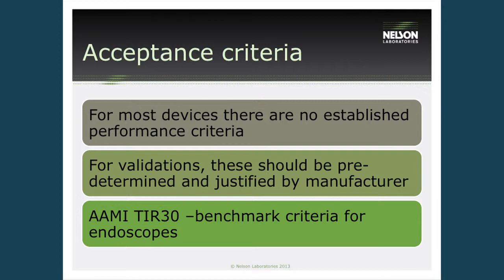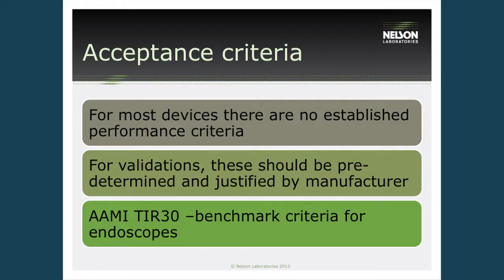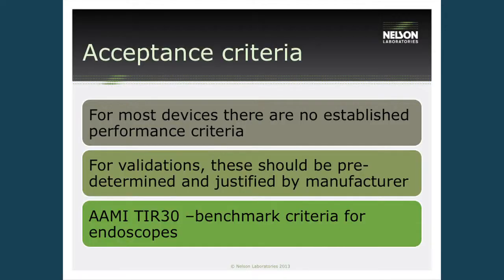So the other thing that we need to determine is acceptance criteria. This needs to be determined prior to the start of a cleaning validation. And this is a little bit difficult to get the exact numbers that are appropriate. TIR 30 has some basic recommendations in that document, but the problem with those is they are based on one study that was an endoscope. So it's not a lot of information. So a lot of medical device companies are going off some historical data and so on to determine what their acceptance criteria is. But the biggest thing for that is to make sure that they're justified. So whatever is determined by the acceptance criteria is justified.